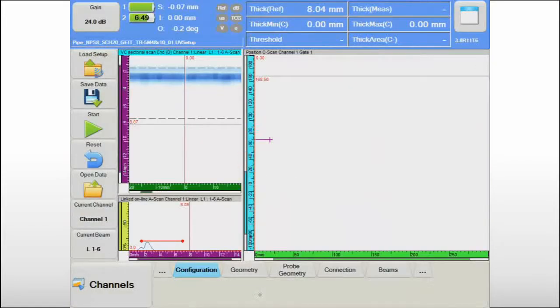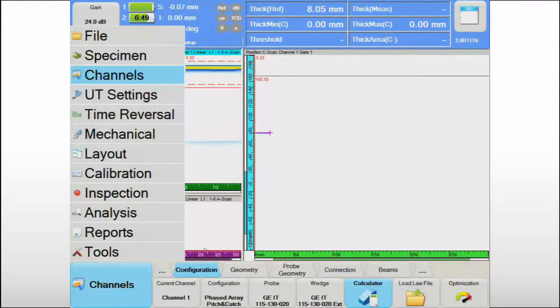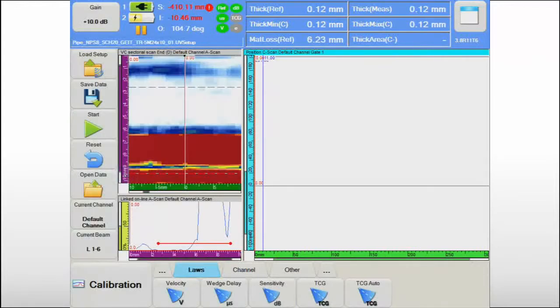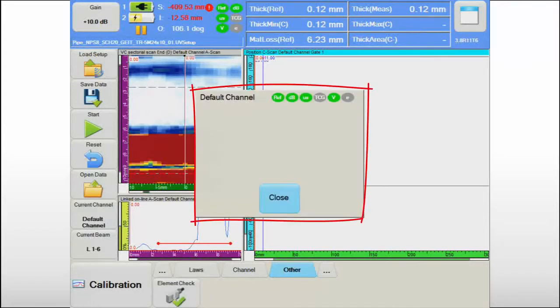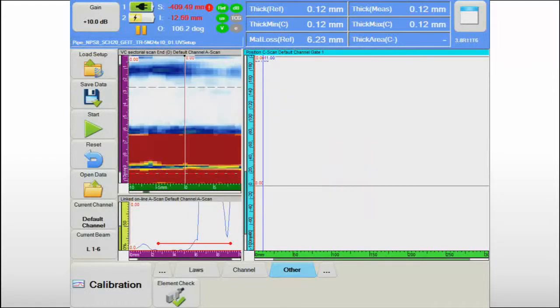Accurate thickness measurements require a robust calibration process. The TOPAZ16 provides user-friendly calibration routines. All this is easily executed, and the valid calibration status is confirmed on the screen. The typical screen organization for corrosion mapping includes a position or amplitude C-scan view, also called the top view, and the corresponding A-scan and B-scan views.